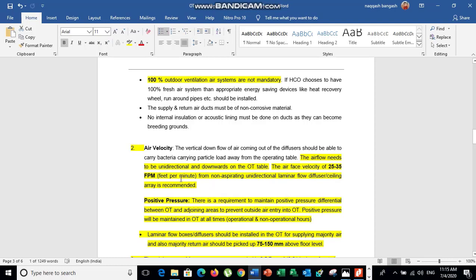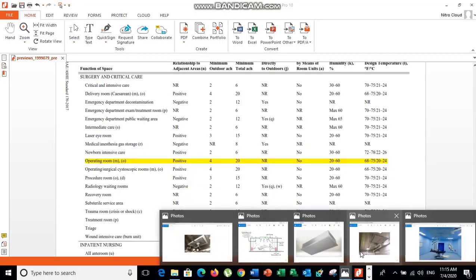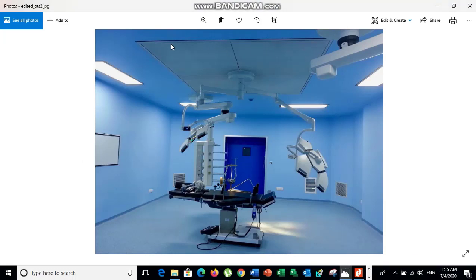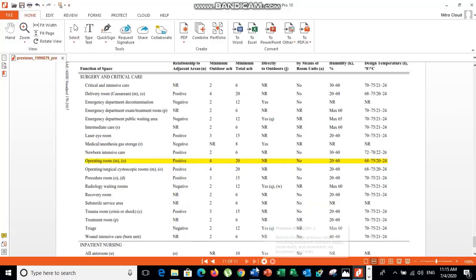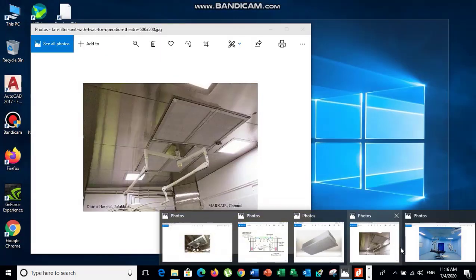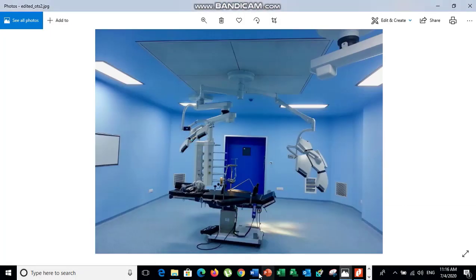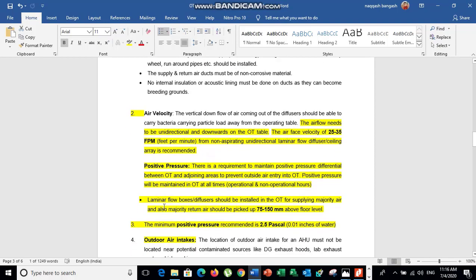The second main concern is air velocity, which should be 25 to 35 FPM in the operation theater. For this, a non-aspirating laminar diffuser made of SS304 material or aluminum should be used. If the air velocity is increased beyond this range, it can disturb the patient during the operation.